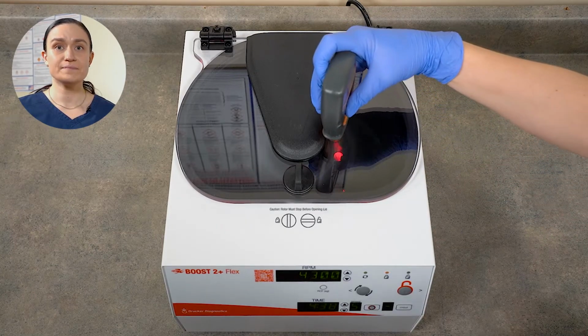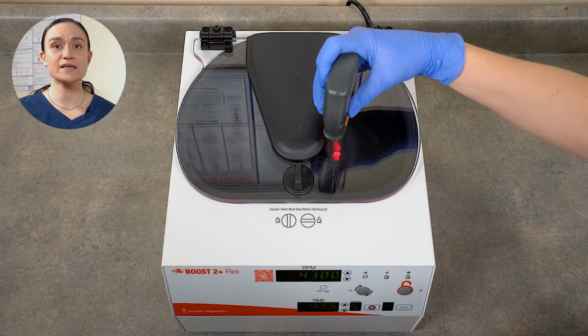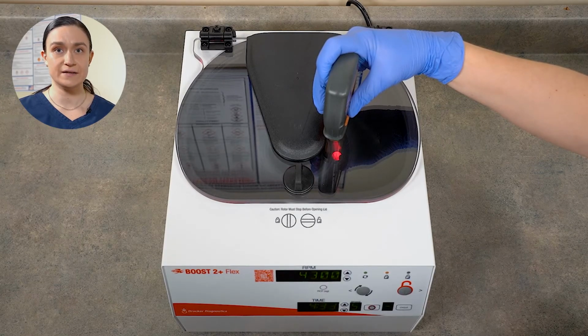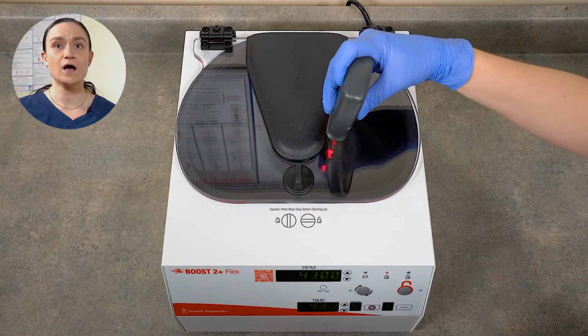Once that countdown timer has started, use your phototachometer and point it down through the lid, right up against the black part, but making sure that the tachometer is looking down through the clear lid. You should receive a reading almost immediately. And that's all there is to cleaning and maintaining your Boost 2 Plus Flex centrifuge.